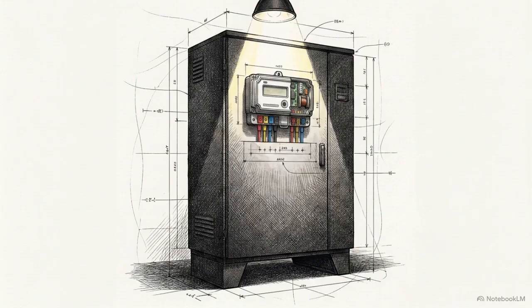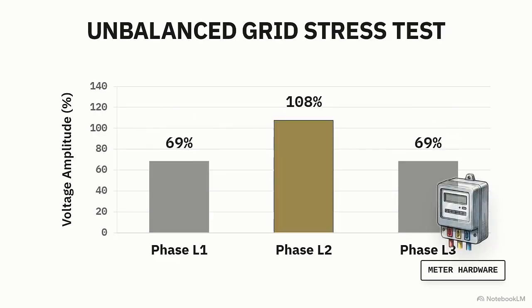High-stakes revenue meters require a specific edge case verification, known as the creep test. This stress test ensures the meter does not record energy usage during extreme, unbalanced grid conditions. You execute this by injecting exactly 120% of the meter's rated voltage, while simultaneously holding the current at absolute 0 amps. To pass, the meter must prove it remains completely dormant. You verify that there is absolutely 0 pulse direction or rotation under this overvoltage state. Any pulse recorded during this state indicates a logic flaw. That specific failure results in false, artificially inflated billing for the consumer.